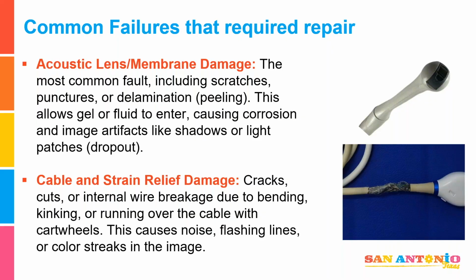Common failures, and this is where we want to talk about how you can look at them, right? We've said to inspect them. Acoustic lens and membrane damage. You can have holes in the lens, especially if they're doing biopsies. They'll use the needle guides and stuff, and you'll see that they'll get damage to the lens. If they clean them with a harsh chemical or even a rough cloth, sometimes I swear they're using sandpaper to clean them because the corners are all worn off and exposed right to the crystal. Which causes a lot of problems with image quality and electrical safety.